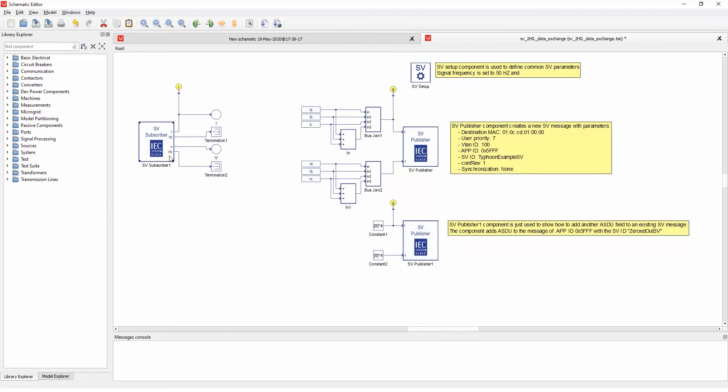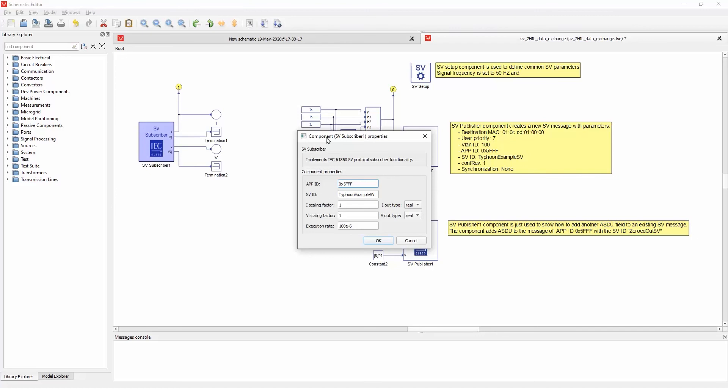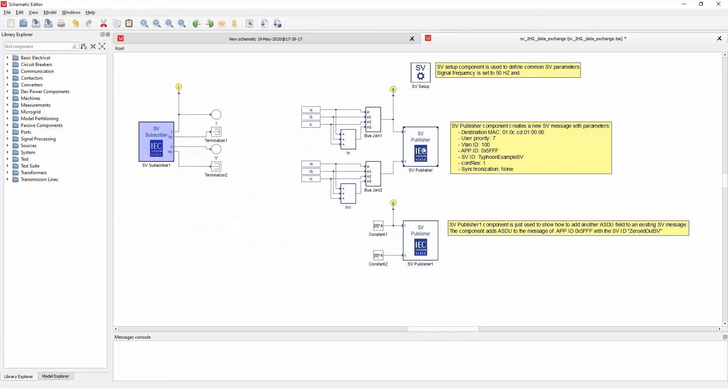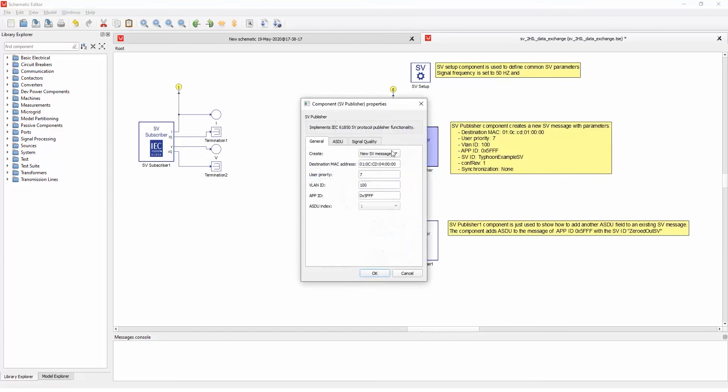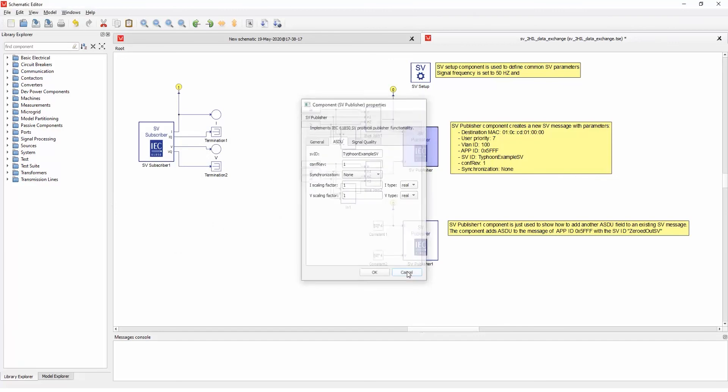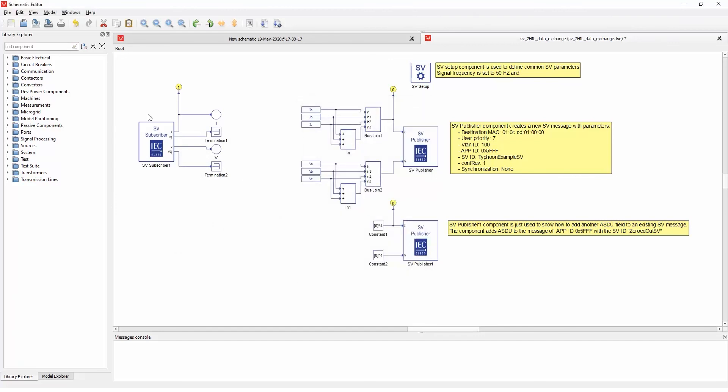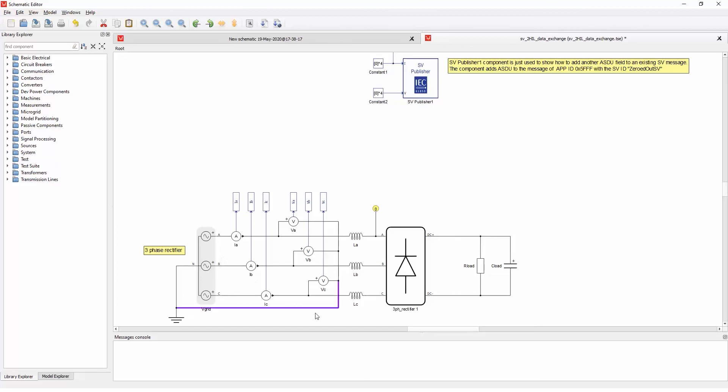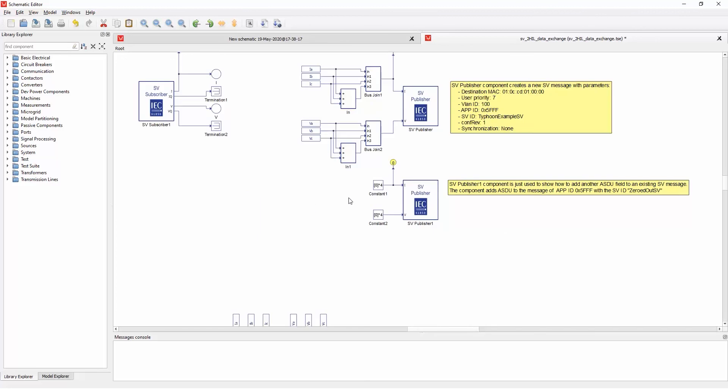And in subscriber, we subscribe to one message that has the ID of the message that we defined and the sample value of TyphoonExampleSV, which is this ID that we defined here. And basically, the first HIL will send the message and the second HIL will receive this message of these currents and voltages.